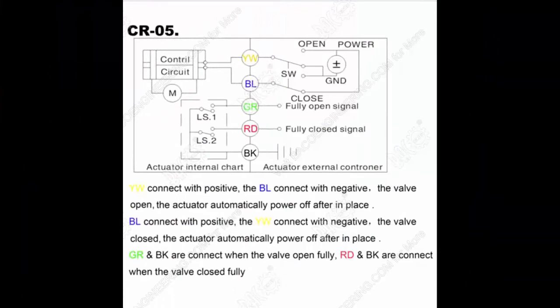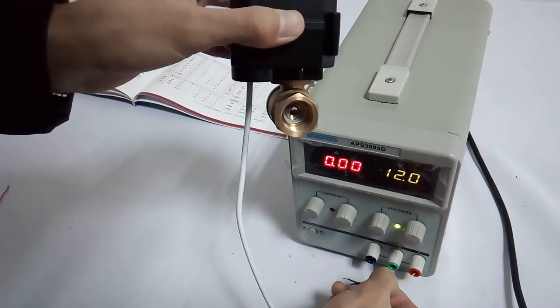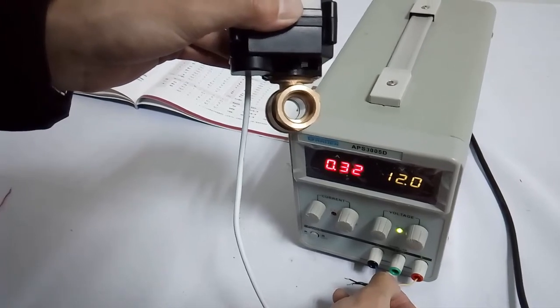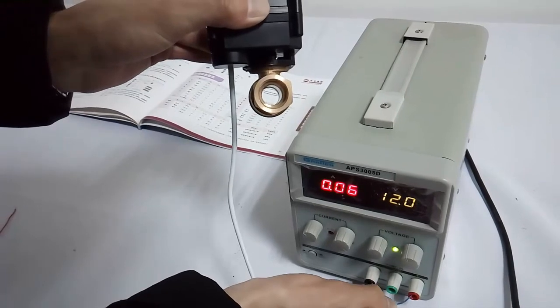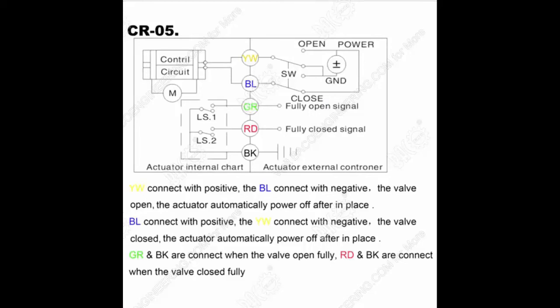Wiring diagram CR-05: It has 5 wires — yellow, blue, green, red, and black. When yellow is connected to the positive pole and blue is connected to the negative pole, the valve will be opened. When yellow is connected to the negative pole and blue is connected to the positive pole, the valve will be closed. When the valve is opened, the green and black wires are connected. When the valve is closed, the red and black wires are connected. The green, red, and black wires must be connected to the signal device first before the yellow and blue wires are connected to power, otherwise the actuator could be damaged seriously.